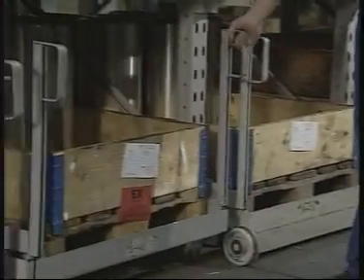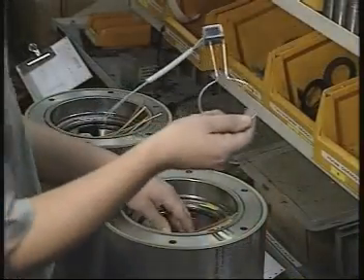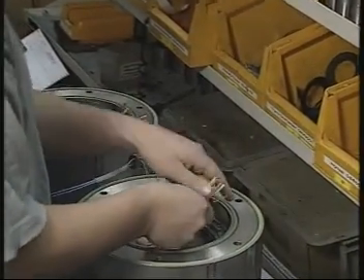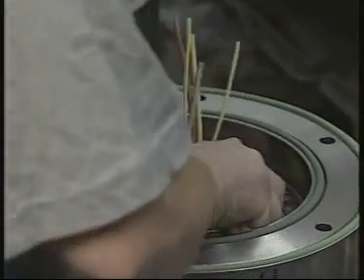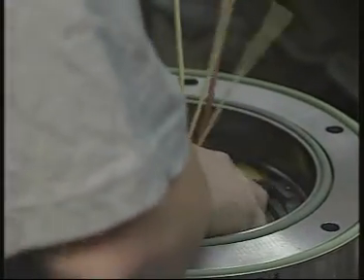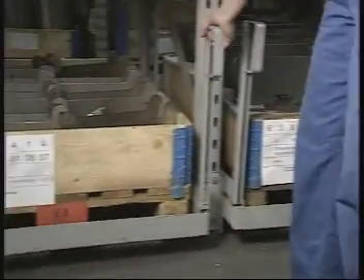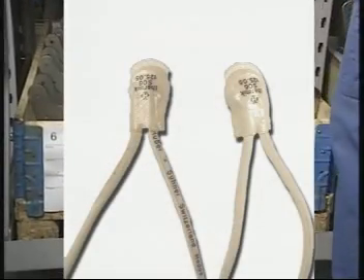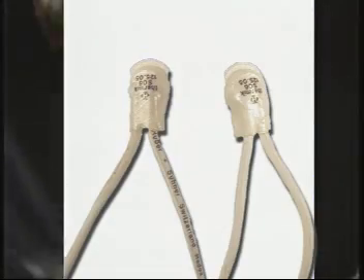All work on the explosion-proof motor section, including the installation of electrical connections, must be carried out by personnel who are EX-proof qualified and authorized by Flygt Corporation. Work outside the approval parameters, for example changing propellers or plug-in seals, can be done by non-authorized personnel. Thermal contacts must always be used on EX-approved mixers because of the approval conditions.